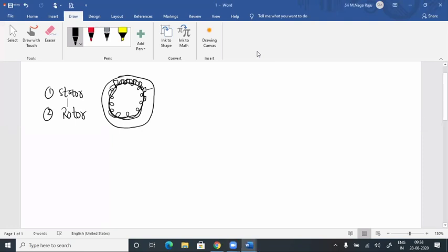And this is about the slots, and the material used for the armature core is silicon steel. Okay, so we have discussed why we use steel and why we add silicon to the steel. Okay, so the silicon reduces the eddy current losses. Steel has a low hysteresis coefficient, so hysteresis losses will be minimized by using steel material. So overall, silicon and steel reduce the iron losses. Okay, and the stator core is laminated.